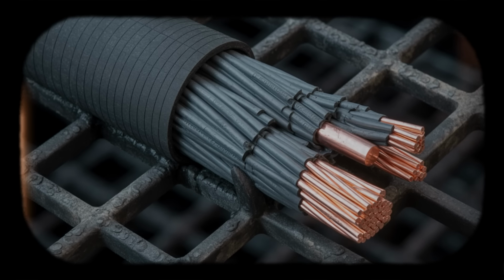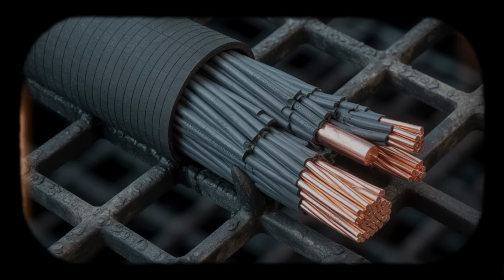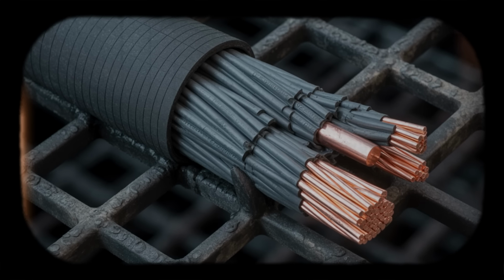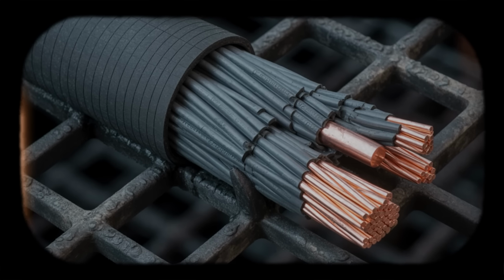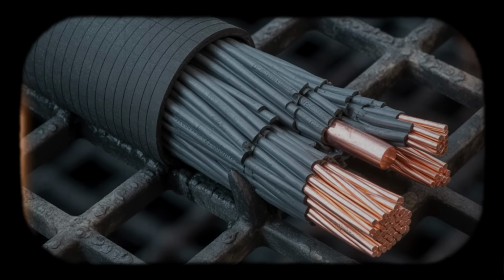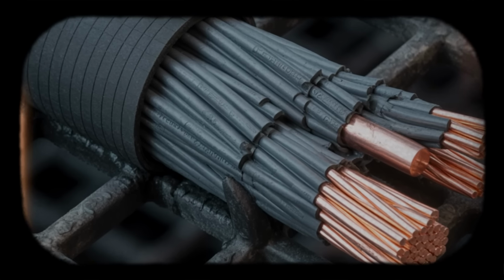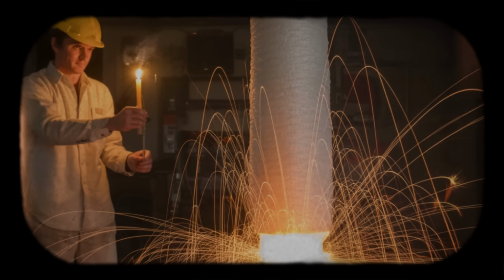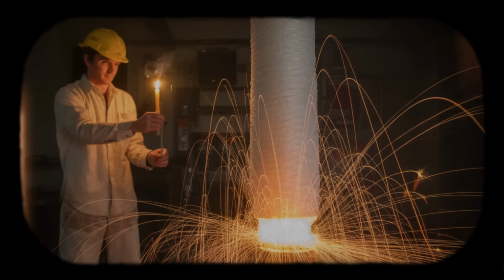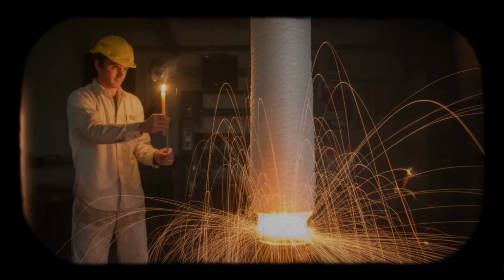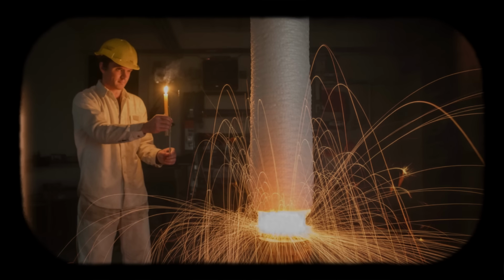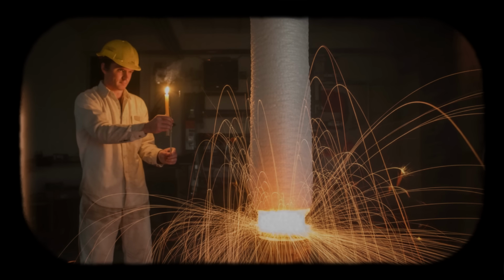Design assumptions about fire behavior in nuclear plants did not anticipate this outcome. Regulations in 1975 focused on fire prevention rather than fire propagation. Cable insulation materials were not required to be flame retardant. Penetration seals were not required to be fire-rated. Cable trays were not required to have fire barriers between trains. Detection and suppression systems were minimal in areas like cable spreading rooms that did not contain obvious ignition sources.